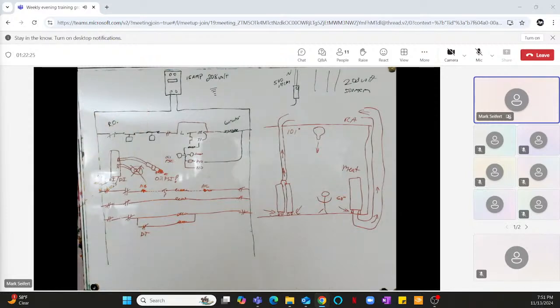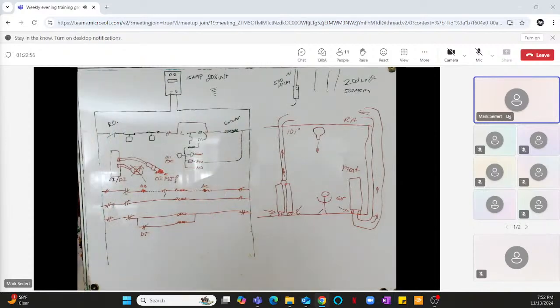other stuff's not going to work properly. Obviously, if you don't have a CT and it's calling for the compressor and it's not running, it's going to trip on oil fail, even though it's off on head pressure. So just because the controller says it's off on oil fail doesn't mean that's it and you walk out the door. Follow what I'm saying? You might push the oil, might clear the oil, reset, and say, all right, I'm out of here. Well, hold on there. That compressor may not be coming on. You've got to make sure it's coming on.